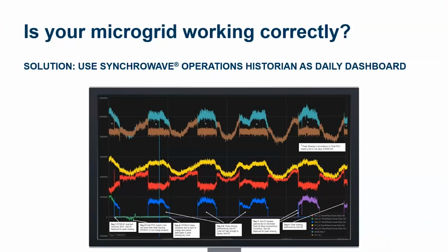During the cycle of its discharge for peak demand shaving, it suddenly turned off. We'll talk more about that behavior in a moment. It turned off. The PowerMax controller then automatically started a 2 megawatt gas reciprocating engine right next to it to compensate for the loss of the battery, still meeting the peak demand shaving objective.